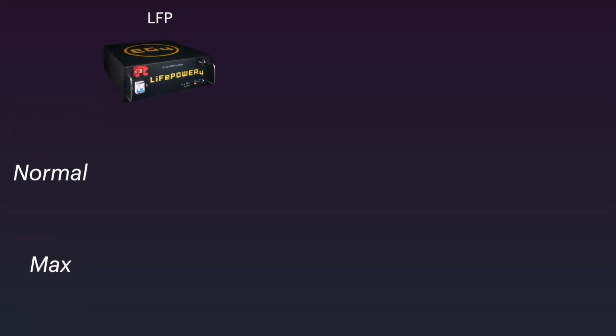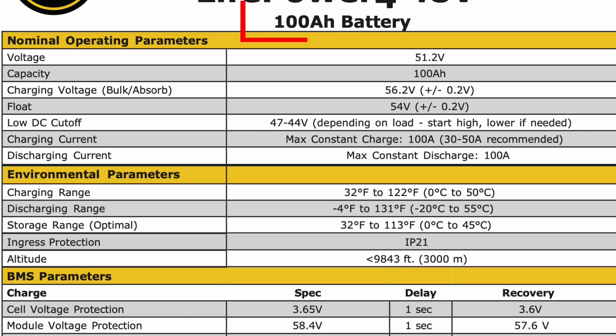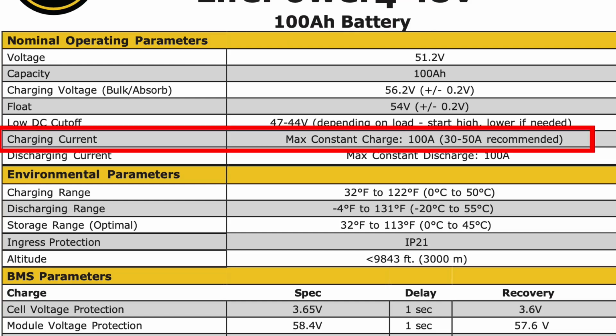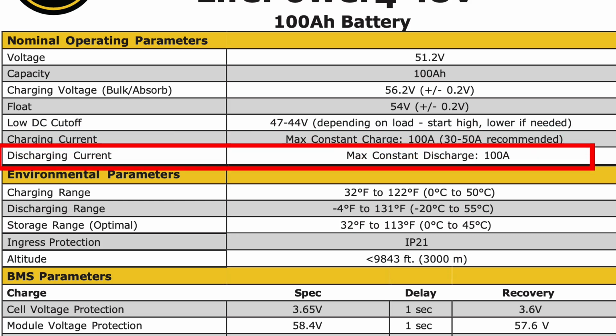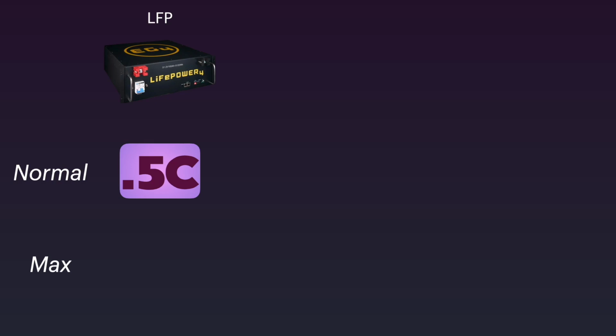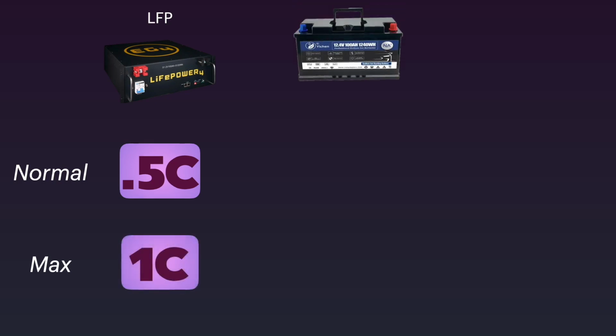Let's start with the lithium iron phosphate battery. This has a capacity of 100 amp hours. The maximum constant charge is 100 amps, so 1C, but they recommend 30 to 50 amps, or 0.3 to 0.5C. The maximum discharge is also 100 amps, or 1C. Our normal charge rate is 0.5C, maximum 1C.